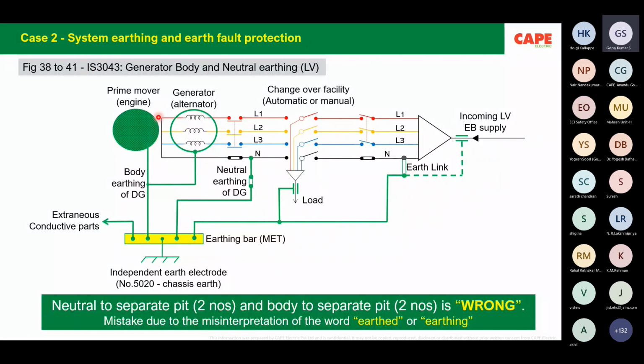For example, the DG where I am rolling the cursor, I'm sure you are able to see that. The body of the DG is connected to a common bus bar. Incoming EB supply, TNCS system, is connected to the same bus bar. Load side is connected to the same bus bar. The same bus bar is connected to extraneous conductive parts such as pipe fittings or material, the frame of your building. Then an independent earth electrode.